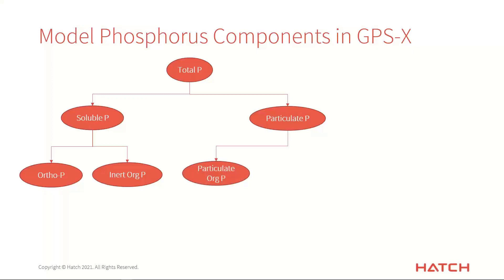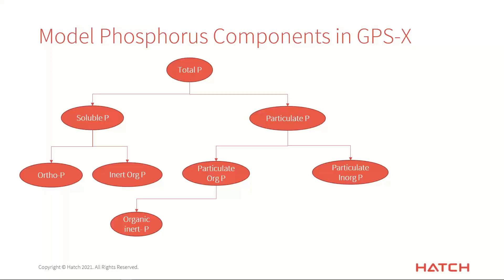The particulate P breaks down into particulate organic and inorganic phosphorus. The particulate organic phosphorus has a part associated with inert COD that passes through the plant without being affected by the biology — parameters you can adjust in the influent characterization. We also have the stuff associated with the biomass: poly-P, which is the form of phosphorus stored and removed through the bioP process, and biomass P, which is phosphorus taken up as a nutrient for growth — not only by the PAOs but by all biomass in the activated sludge process. Even regular heterotrophs take up a small amount of phosphorus when they grow.